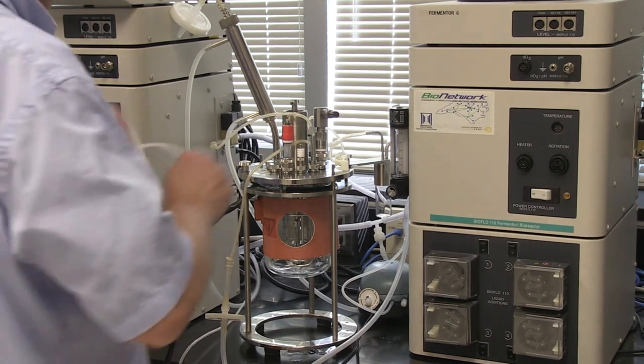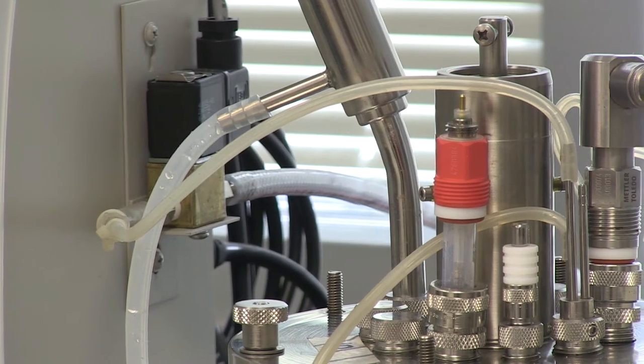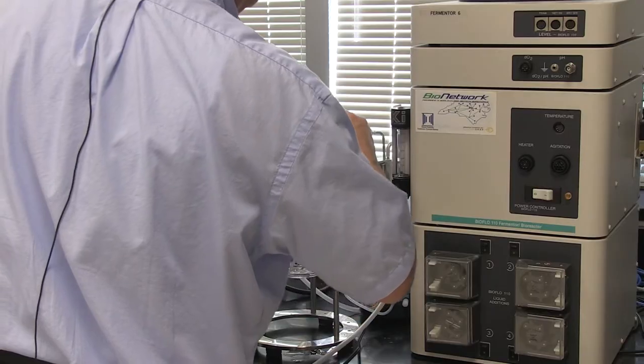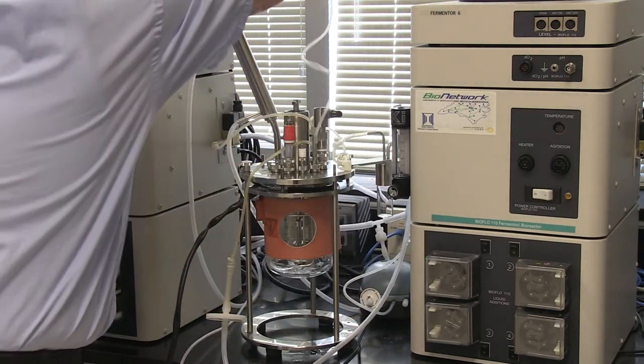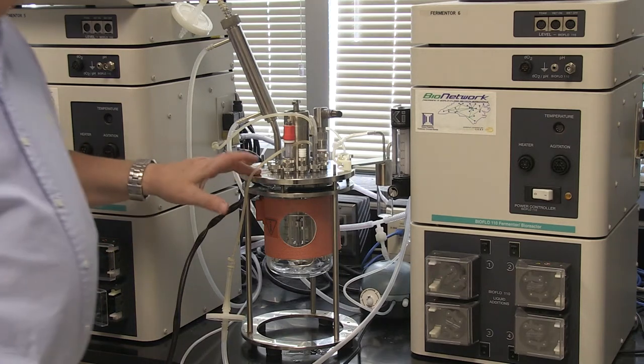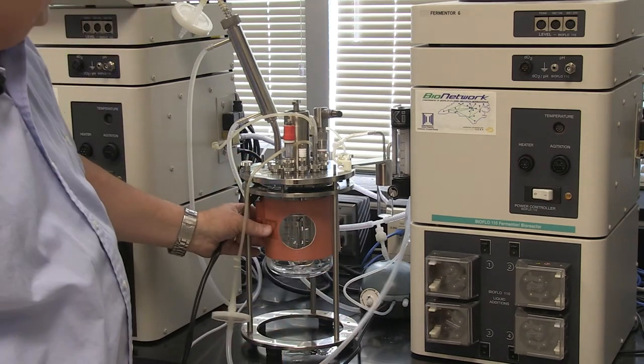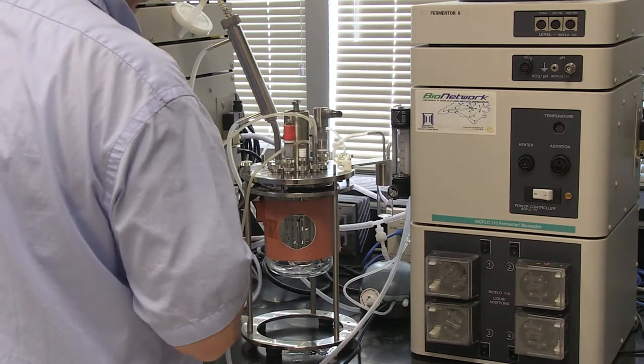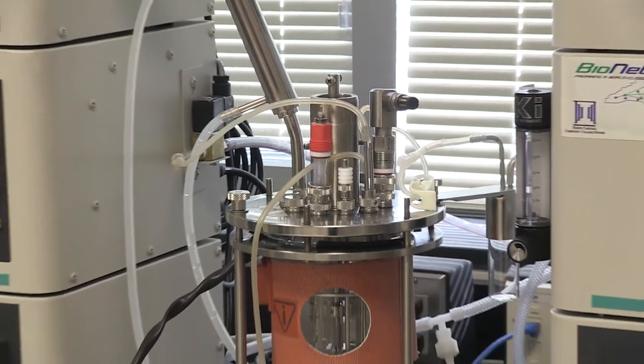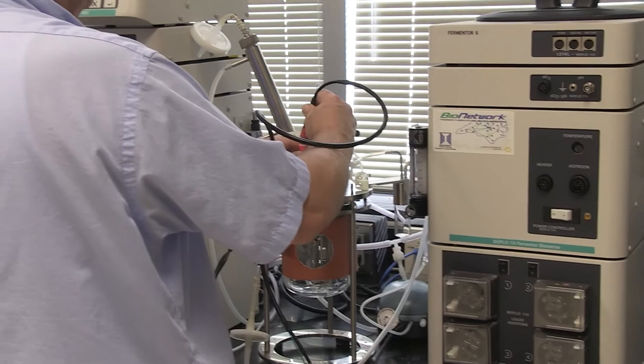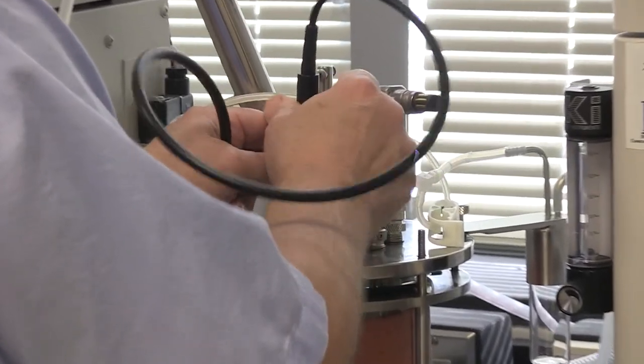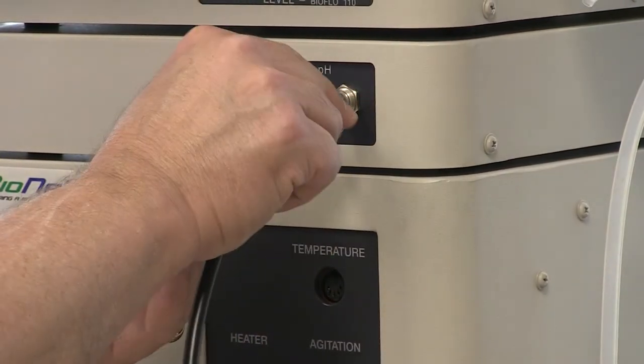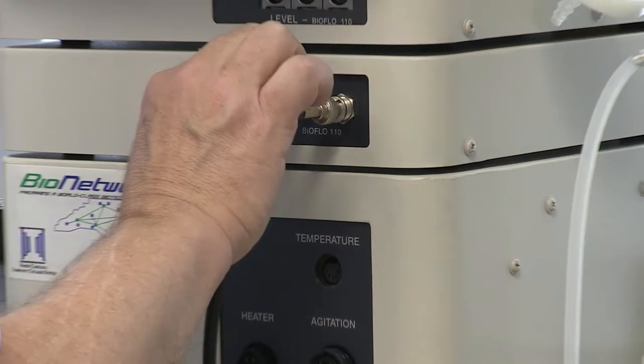So now we've got the air loop for the sparger, and we've got the water loop. Let me go ahead and attach this drain line, to go to the drain. So now we've got our water loop. We've got our heating blanket on here. We've got our water. We've got our air. Now we need our pH connector. So this goes on to the shorting cap position. Screws on. And then this is the connector for the BNC connector and the ground. So it goes on and plugs in there.